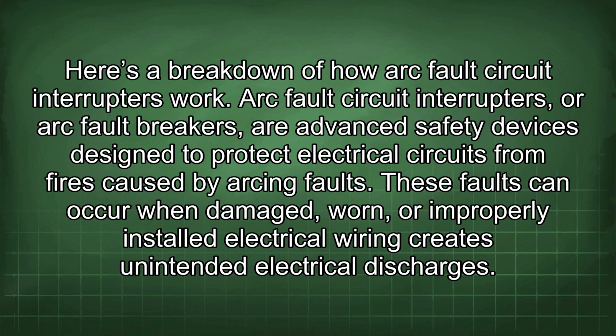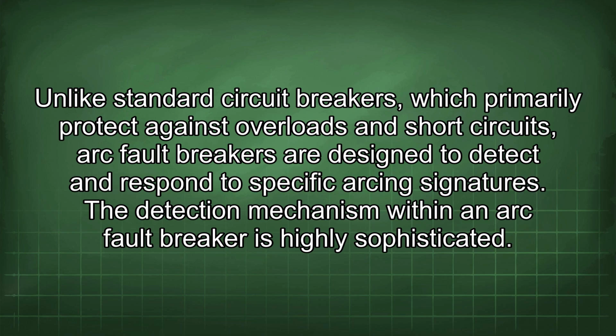Arc fault circuit interrupters, or arc fault breakers, are advanced safety devices designed to protect electrical circuits from fires caused by arcing faults. These faults can occur when damaged, worn, or improperly installed electrical wiring creates unintended electrical discharges. Unlike standard circuit breakers, which primarily protect against overloads and short circuits, arc fault breakers are designed to detect and respond to specific arcing signatures.